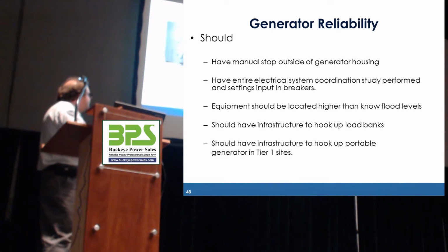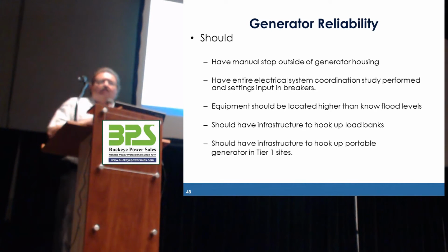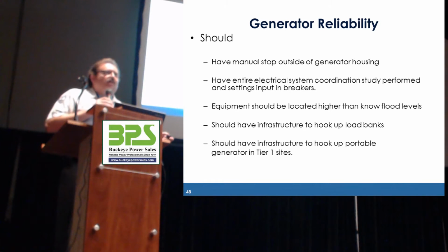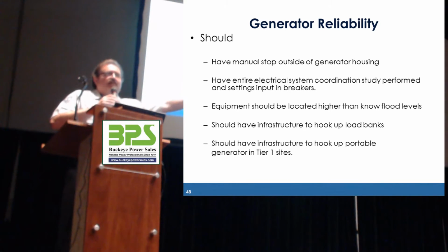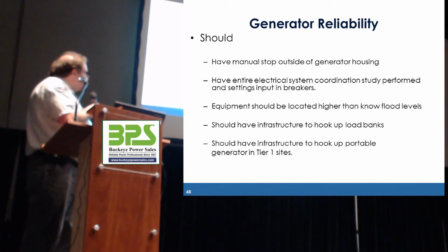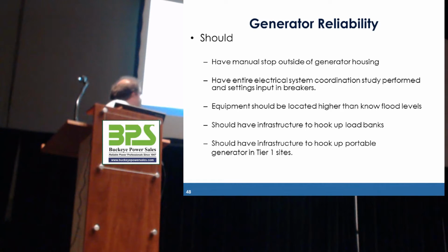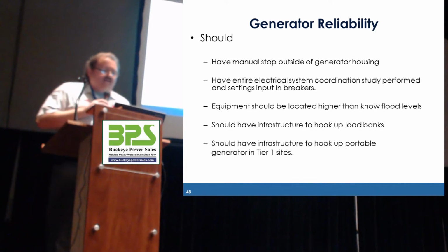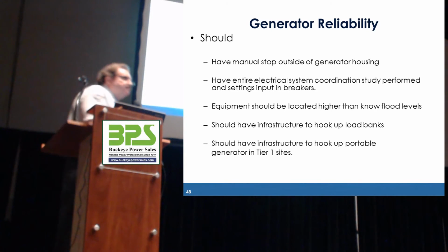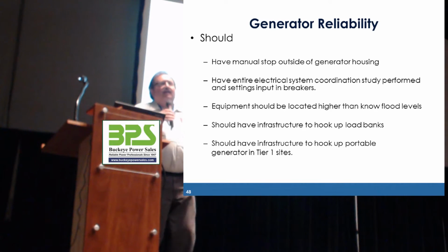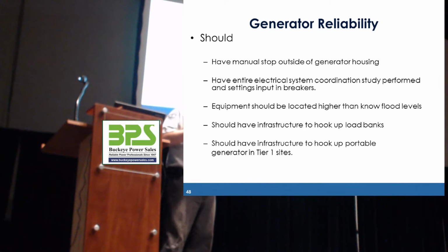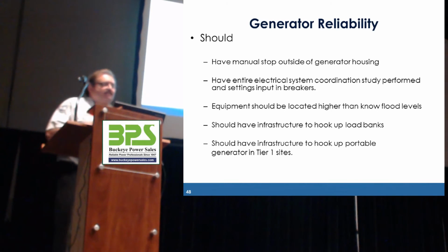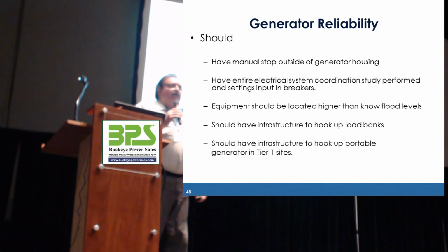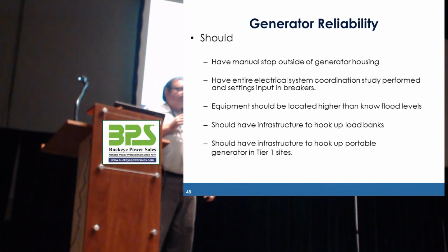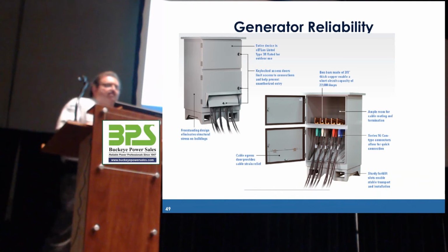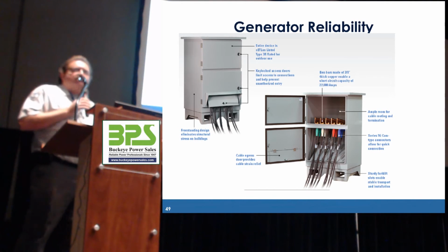In some areas, make sure that your equipment's higher than flood levels. You know, if you're in Johnstown, Pennsylvania, if you've ever been there, the generators are all about 20 feet off of the deck because of the potential floodplain. You need to have the infrastructure to hook up load banks, and you really need to have the infrastructure to hook up portable roll-up generators if you're a level 1, a tier 1 facility. Because once the generator has an issue where you say, okay, hey, I need to load bank this generator, or the generator has to be offline for this cooling system service that's going to take 6 hours to accomplish, that's not the time to be thinking about how am I going to hook up a 1,000 kW rental generator to my facility.